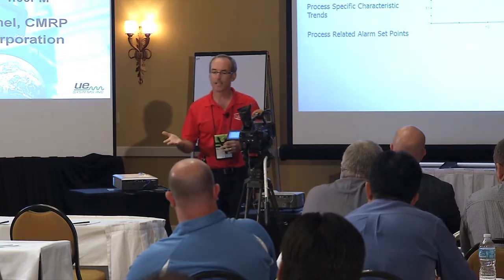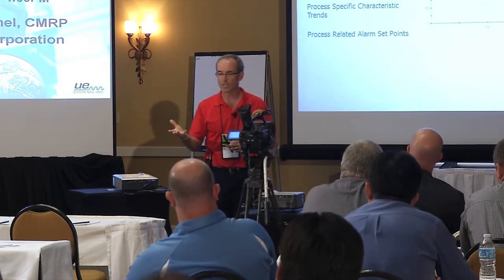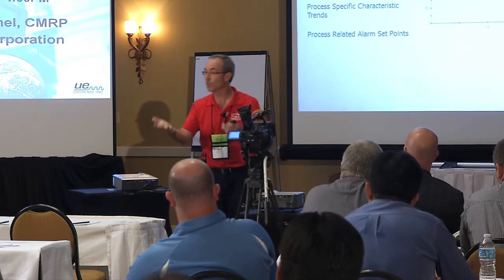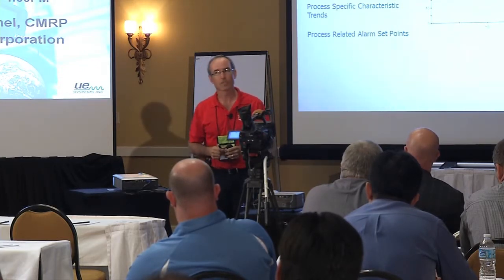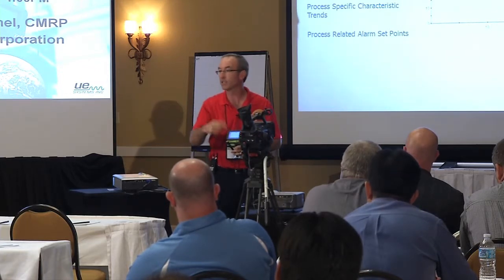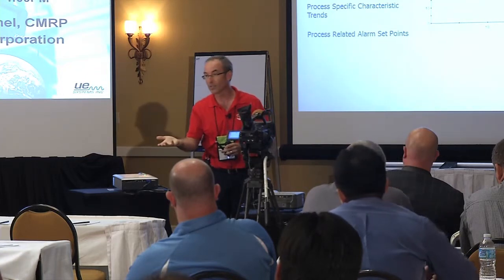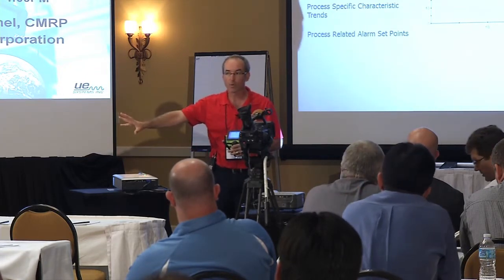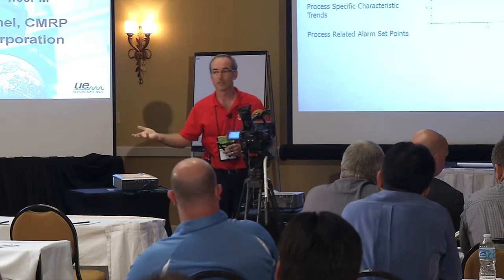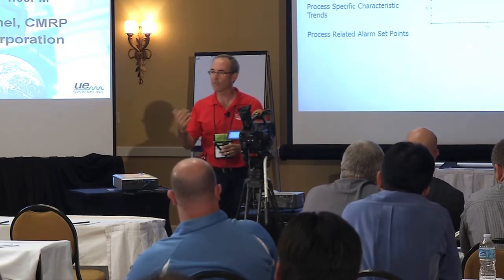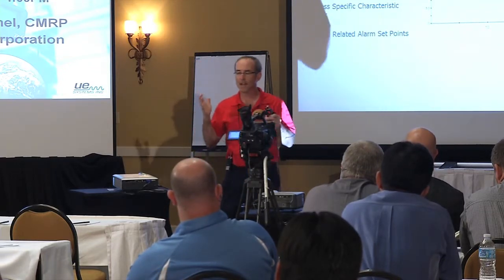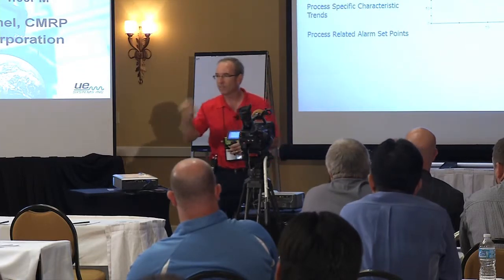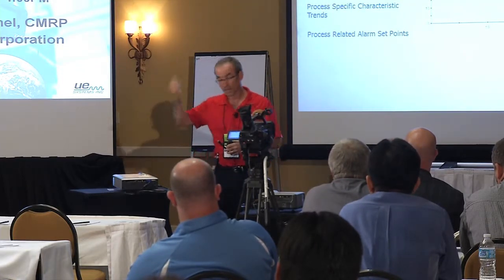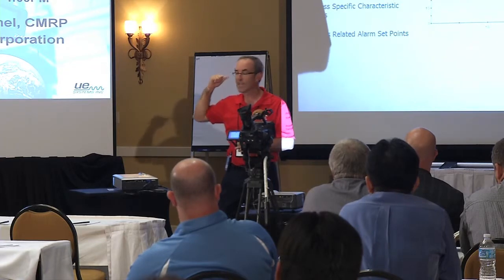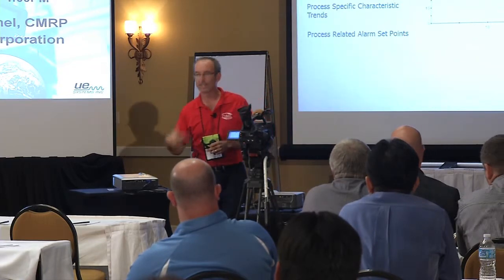I think the biggest thing we've been able to conclude is whether it's the motor or the drive causing a nuisance trip. It doesn't take much, even from an RMS perspective—meaning not the microsecond transient rise time of an IGBT, but just what the signal looks like going to the motor, what frequency it is and how that's changing. Probably the biggest hurdle we have for VFDs right now is that we haven't optimized our system for speed assessment. A lot of our demodulated captures aren't optimized for drives, and we need to rethink that a bit.